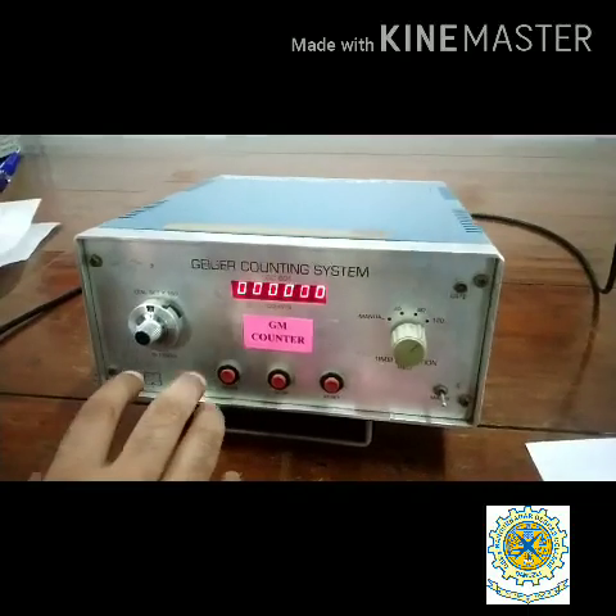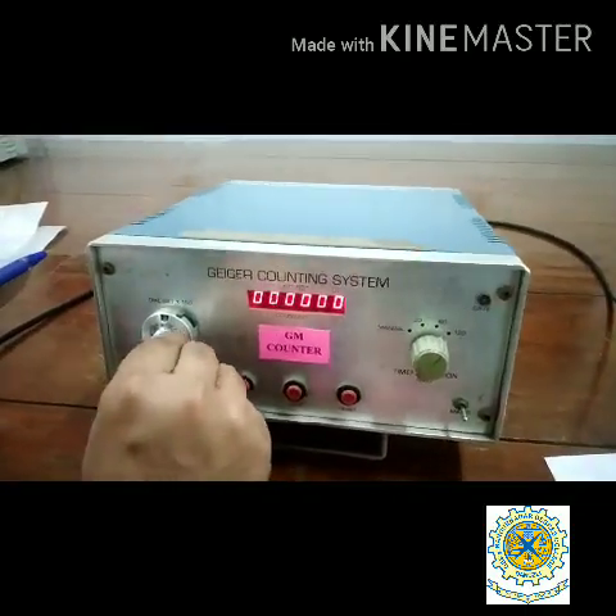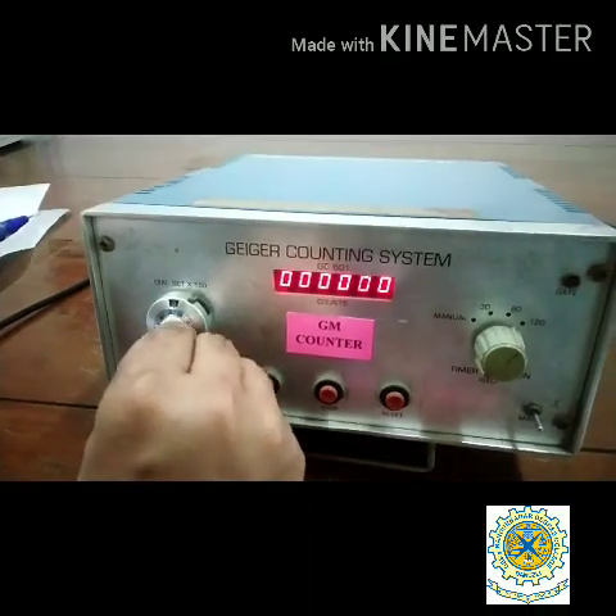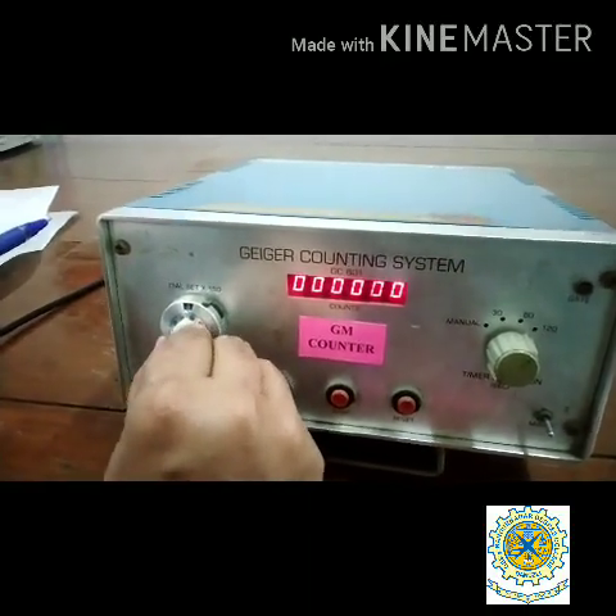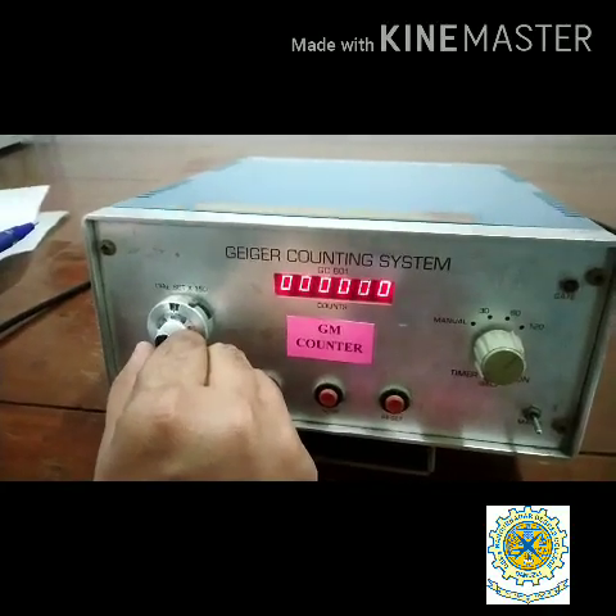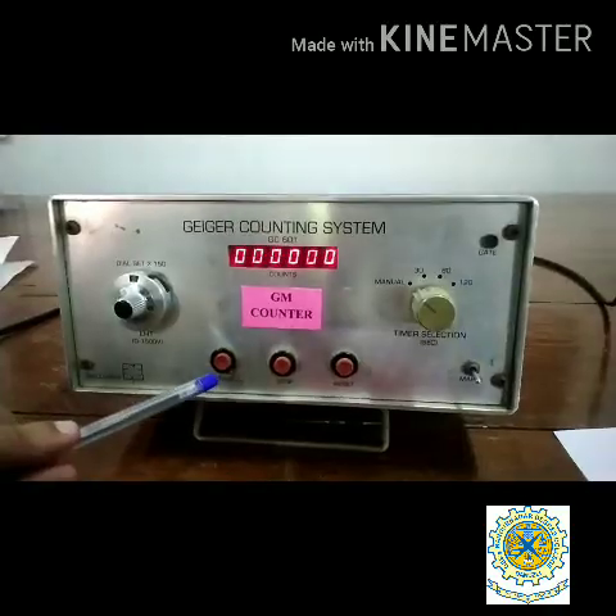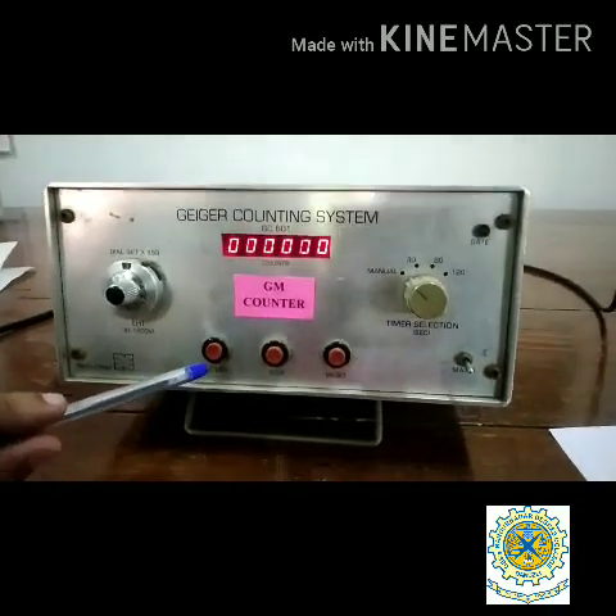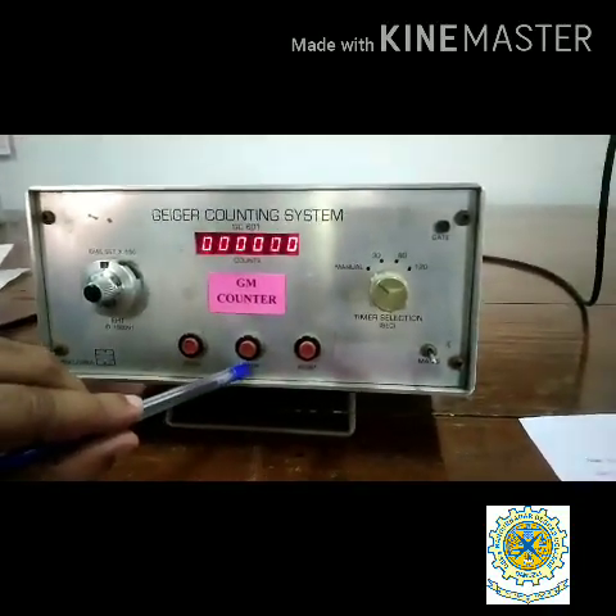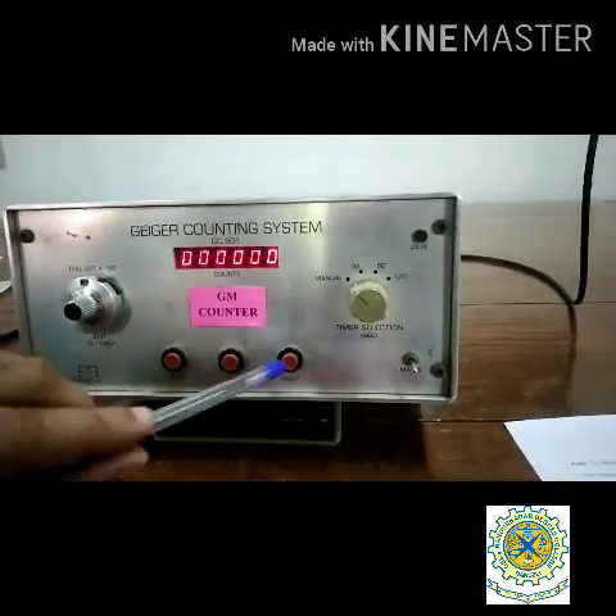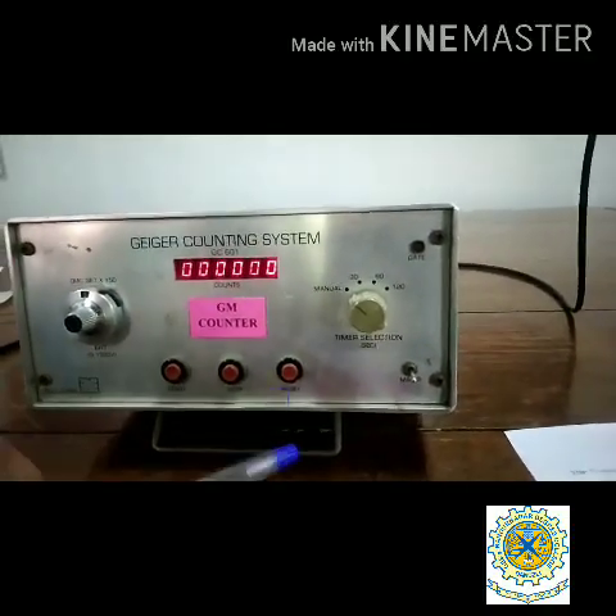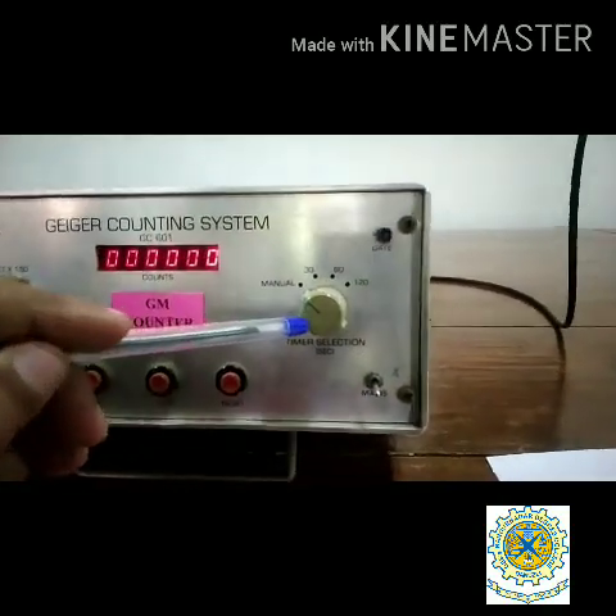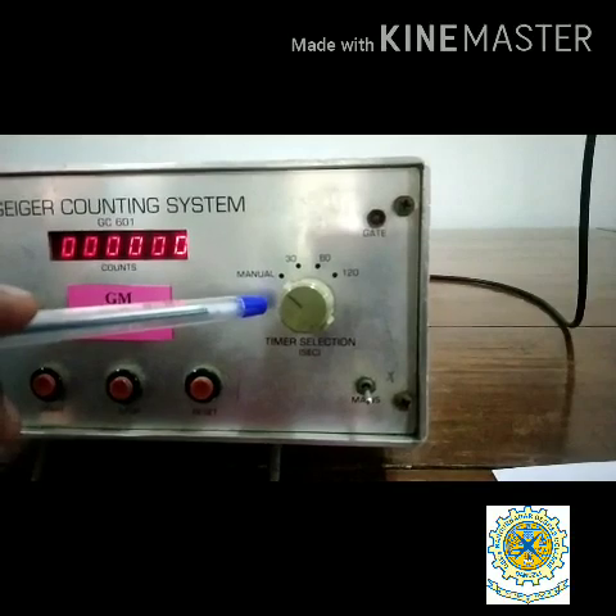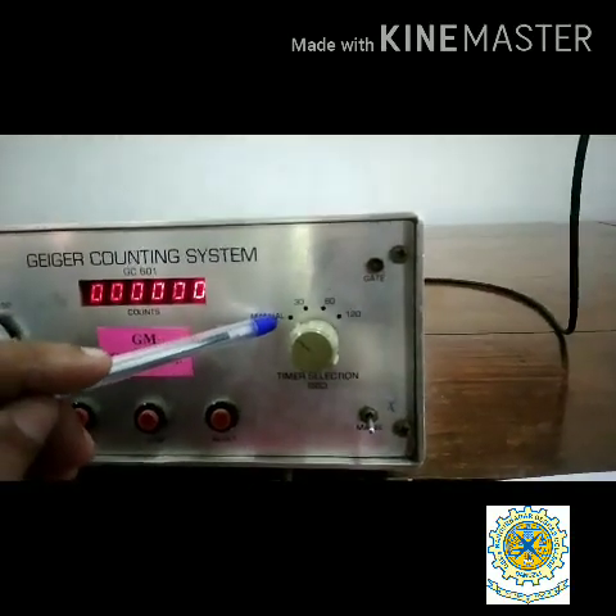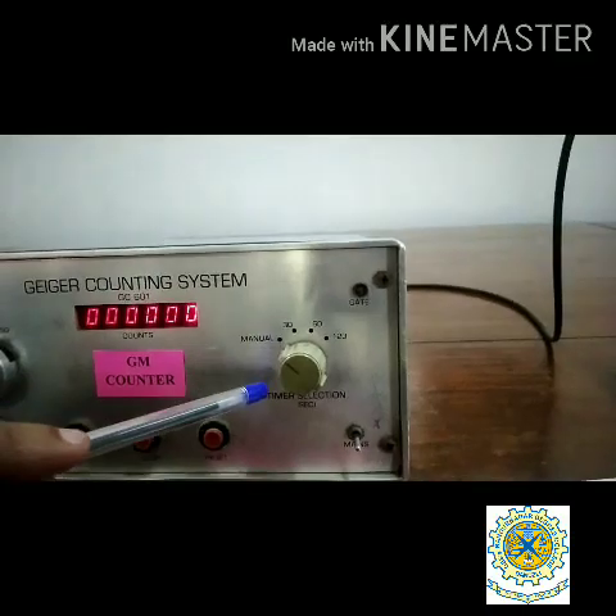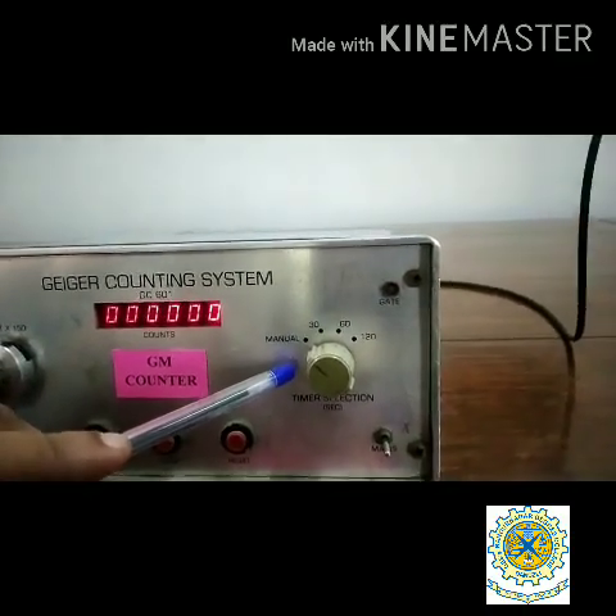For this experiment, we have to set an operating voltage. Operating voltage is the voltage where the instrument has minimum statistical errors. Start indicates that the instrument will run, and stop is to stop the count rate, and reset is to reset the values and run the experiment again. This button indicates the time setting. The manual setting means we can take readings manually, or for days together, to run a longer experiment.